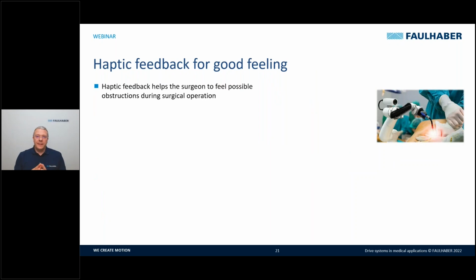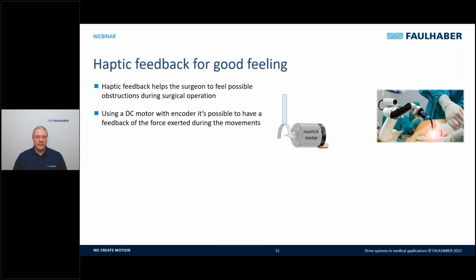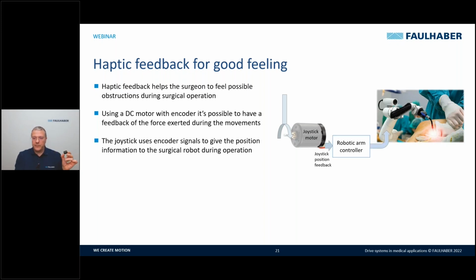The haptic feedback is required because the surgeon has to feel possible obstruction or possible problem during the surgical operation. For this reason, we can use a DC motor with encoder, like for example this unit here, where it's possible to have a feedback of the force during the movement. This is quite easy to obtain because we have, from the feedback of the motor, an encoder. The encoder gives information to the robotic arm controller.